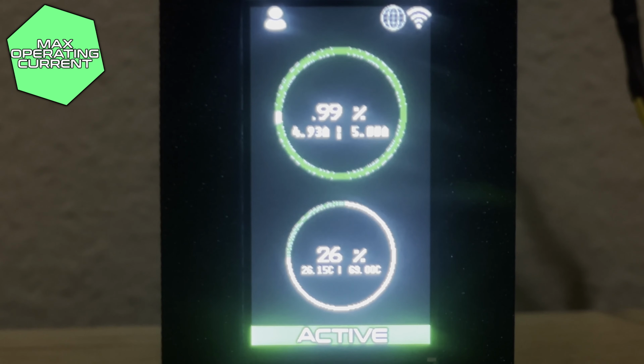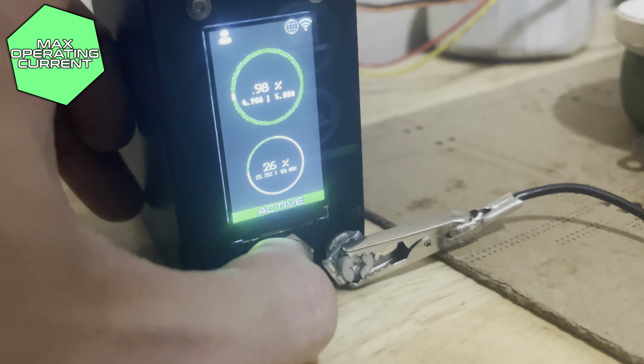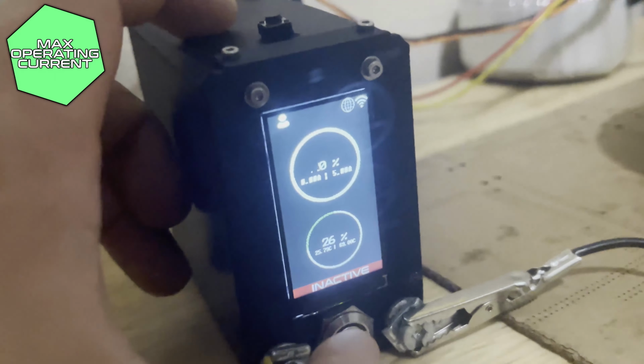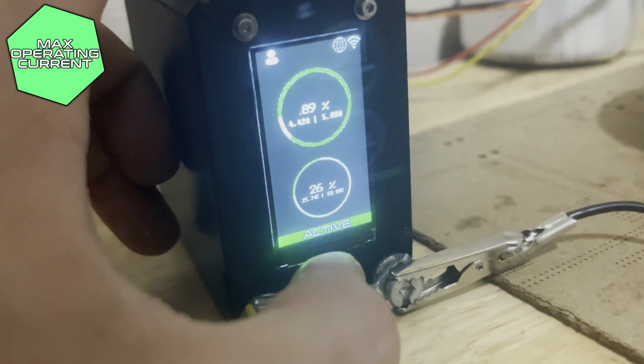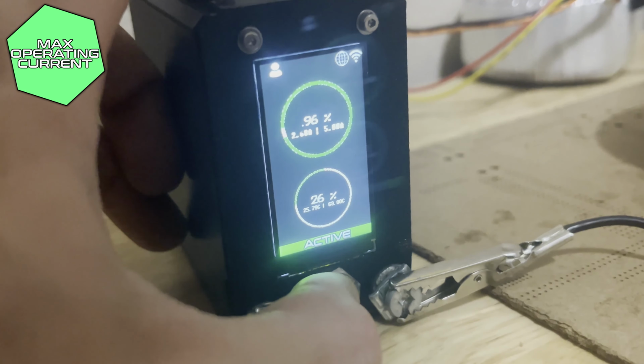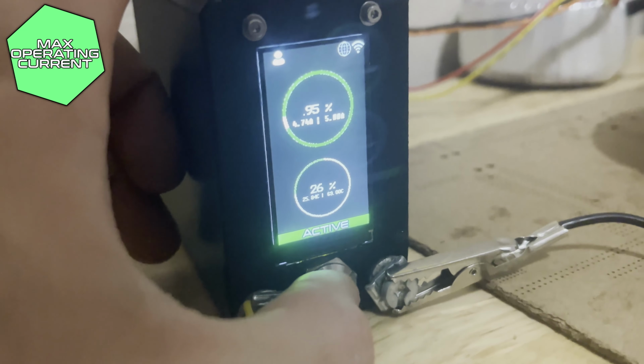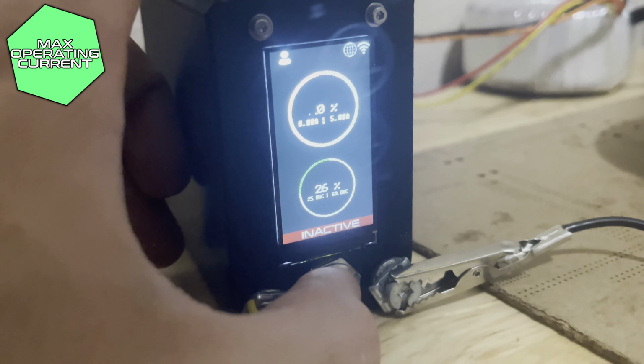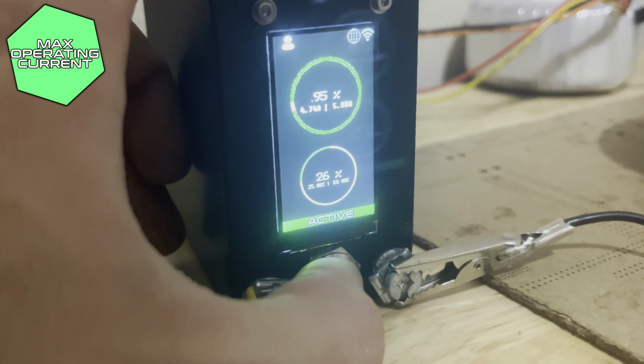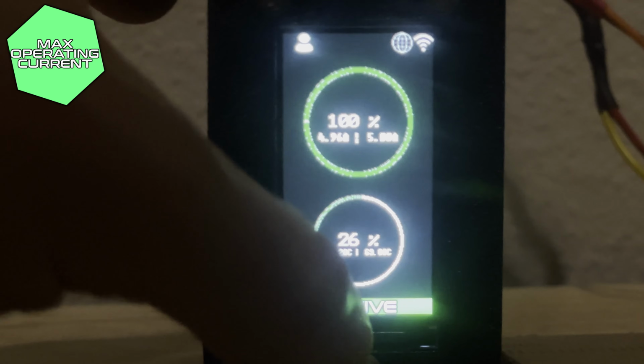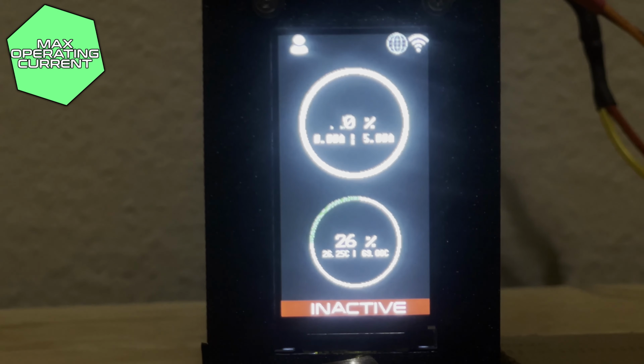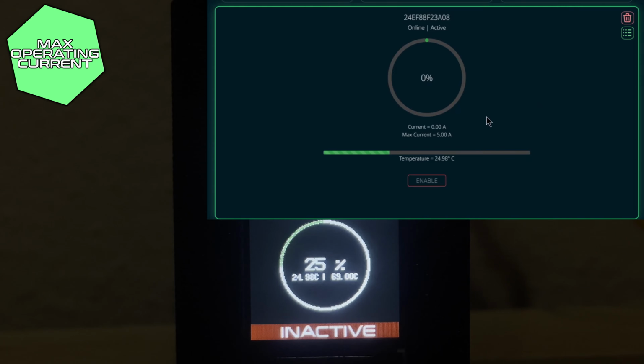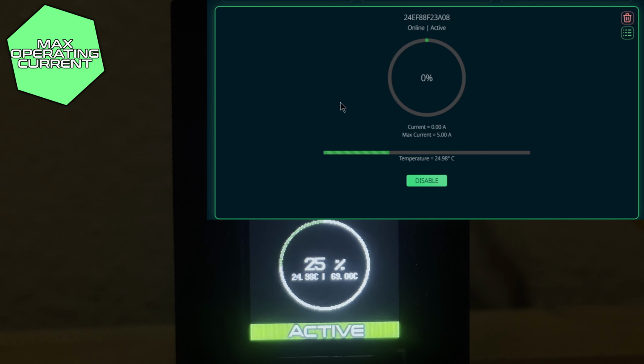Alright, and here's just a showcase of continuous supply current to the load. So it's right underneath 5 amps, so it doesn't automatically trip itself. And I can just come over here and manually trip it on and off. And as you see, every time that the button's toggled, the breaker will flip and no current will be allowed to pass. But then I can toggle it back on, and as we can see, back up to around 4.9 amps passing through. Alright, and so it's currently inactive, but I can come over here on my dashboard, manually trip it, and we're back online. And as you can see, we're reading about 4.9 amps once again.